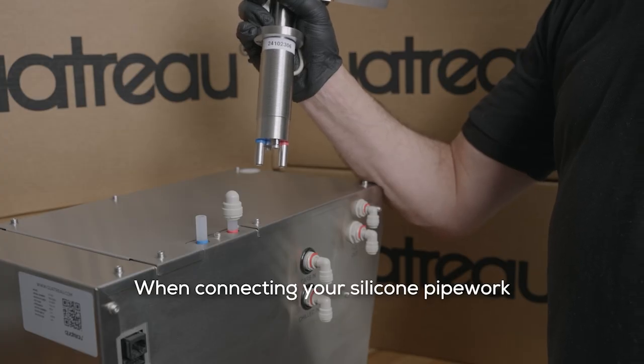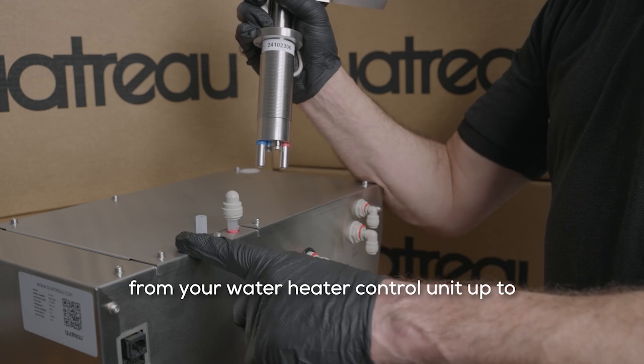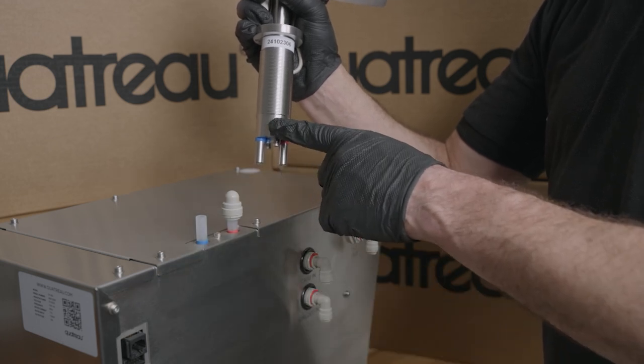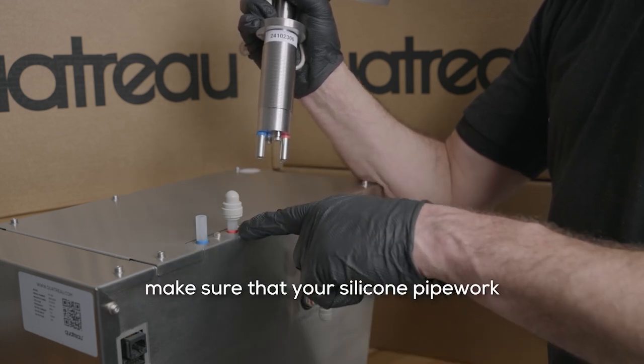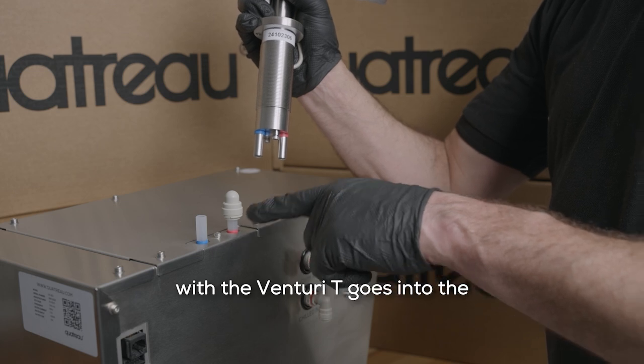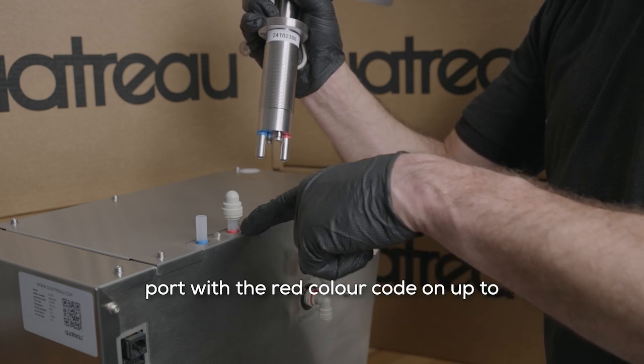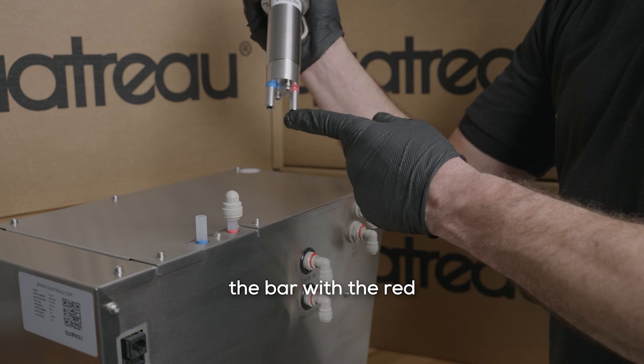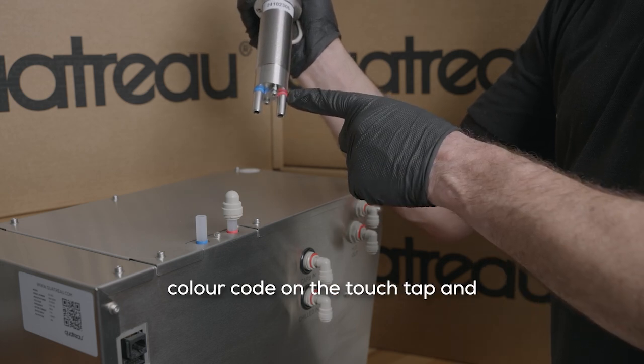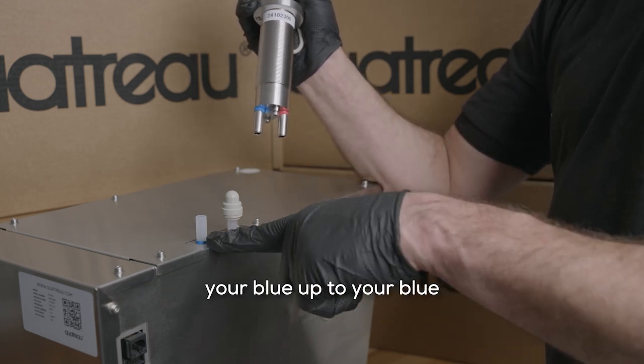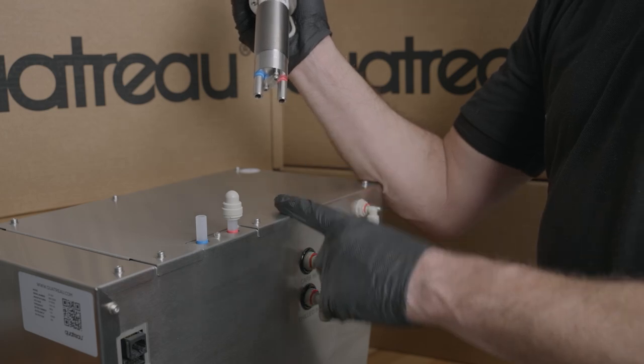When connecting your silicone pipework from your water heater control unit up to your Quatreau TouchTap, make sure that your silicone pipework with the Venturi T goes into the port with the red colour code on, up to the bar with the red colour code on the TouchTap, and your blue up to your blue.